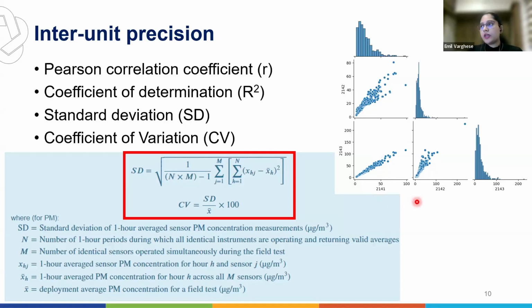In the Python language, it's very easy to just plot a pair plot and see how each of the sensors compares. Here, these are 2142, 2143, 2141, the names of different device IDs from a sensor, and you are comparing whether they are precise to each other. When you compare 2141 to 2143, ideally the points should fall along a 1:1 line if they are precise to each other. This can be seen visually using a pair plot. Additionally, not just with visualization but with certain metrics, we have the Pearson correlation coefficient R, the coefficient of determination R squared, then standard deviation, and coefficient of variation. These are the formulas for standard deviation, SD, and coefficient of variation, CV, adopted from the US EPA guidelines for the different target values.